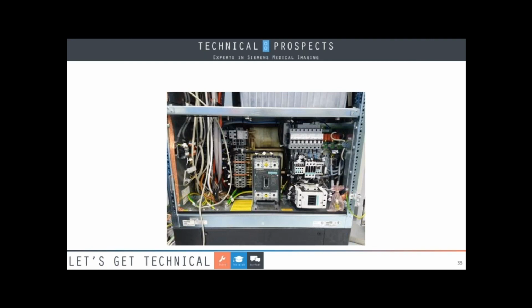Power generally takes place in 3 steps. You have GS, or generator supply. It's going to take 2 of those legs, and it's going to take them to external devices, like your computers or monitors. You have LS, or load contactor, which is also going to use 2 legs to start what they call the charging circuit, so you can make X-rays. And then after those 2 are both good, what we call PS, or your power contactor, is going to kick in with all 3 legs, and then power is going to go throughout the entire system. So if your cabinet did not boot up all the way, you can follow the legs through the relays to see where you've lost power.